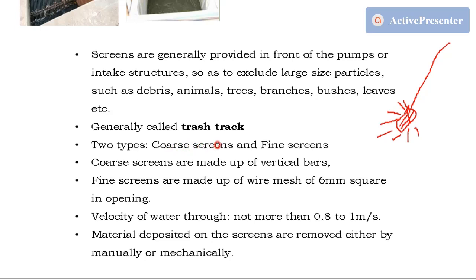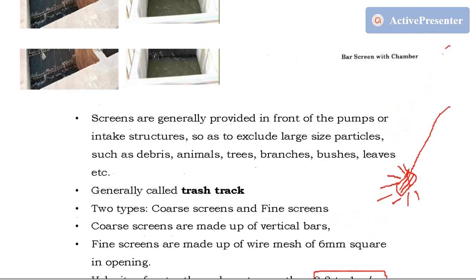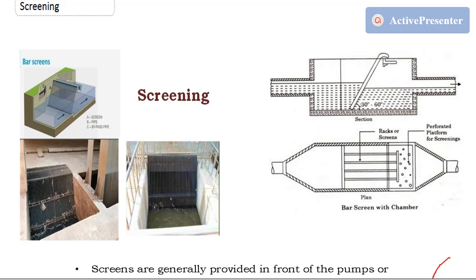There are two types of screens: coarse screens and fine screens. Coarse screens remove coarser material; fine screens remove finer material. Coarse screens are made of vertical bars as shown, while fine screens are made of wire mesh — usually with a 6 mm square opening. In coarse screens there is a vertical opening, not square. The velocity of flow should not exceed 0.8 m/s as the water approaches the screen. Materials deposited on the screen are removed either manually or mechanically by continuously rotating the screens.